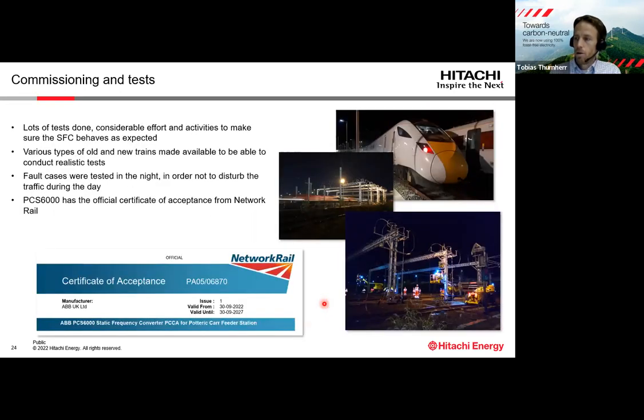Then, because of this first project in the UK, I think quite extensive testing was done. There was a considerable effort put into that, and you can see the pictures here on the right-hand side. A lot of tests were also done at night with different trains that were reserved for testing the SFC behavior. The reason the tests were done at night was that they wanted to ensure that the railway system is not disturbed during daytime when it's normally operating.